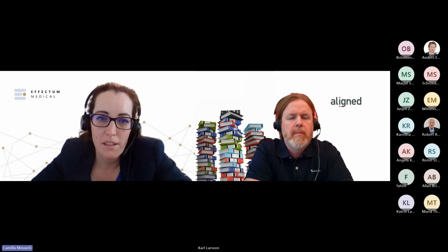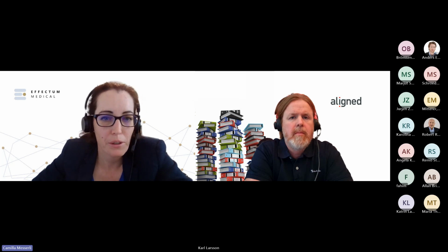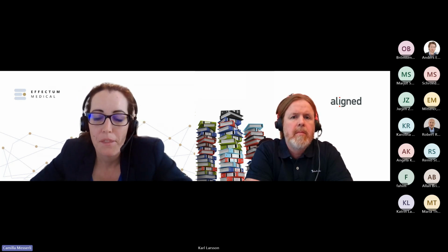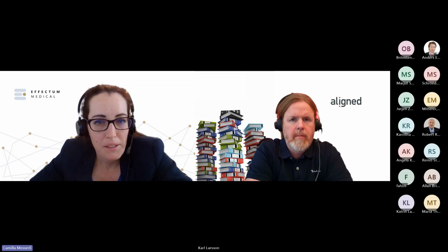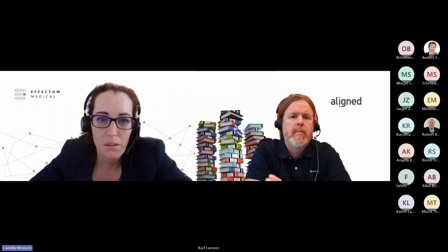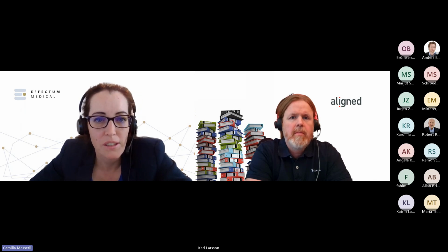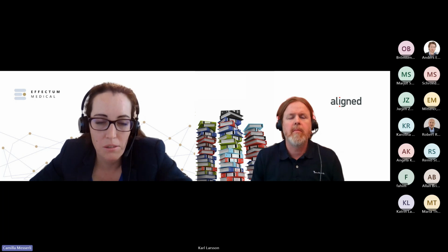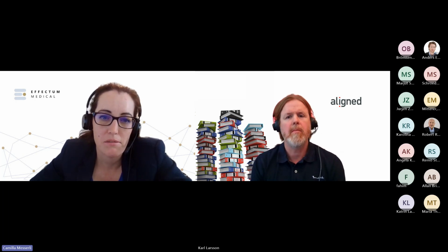So if you don't say in your PMS plan which similar devices exist, and you don't quickly confirm when you start writing the report that those are still the accurate ones, then you won't actually be looking for them in the vigilance cases or databases, and that's an immediate finding. Auditors will straight away look for that as well. So it's not just looking at your own vigilance cases, but connecting the dots to the similar device vigilance cases as well. And that's often missed or just forgotten.